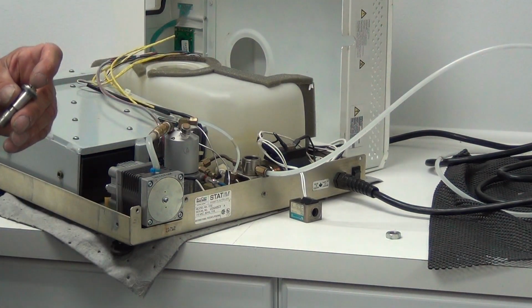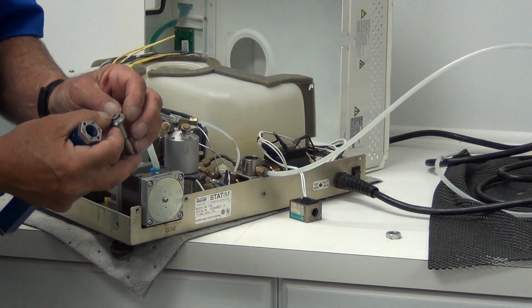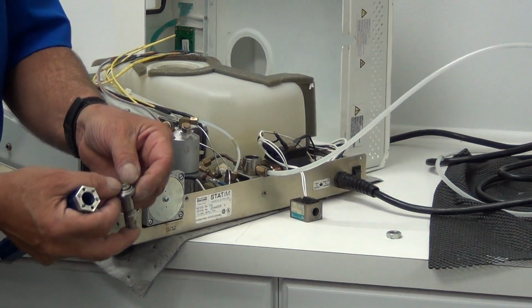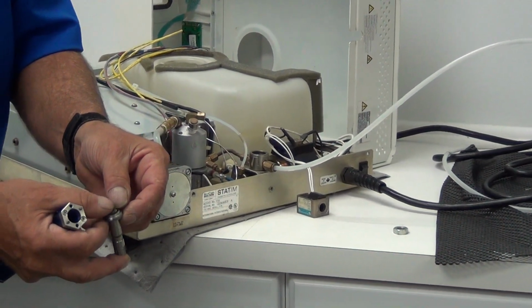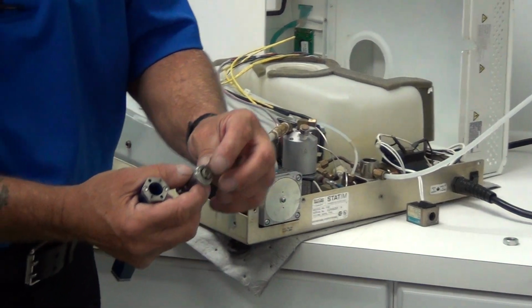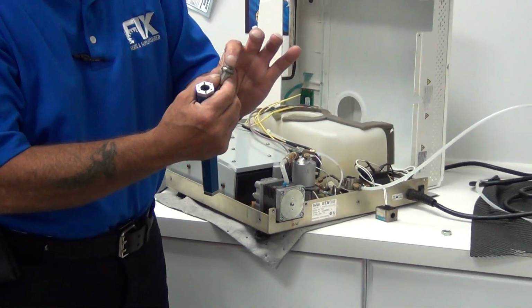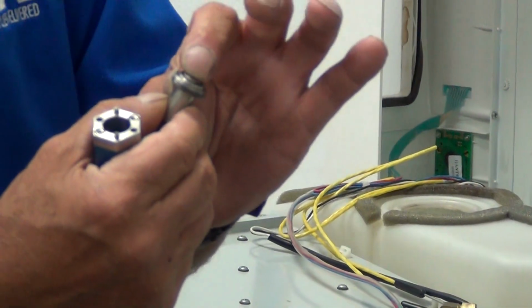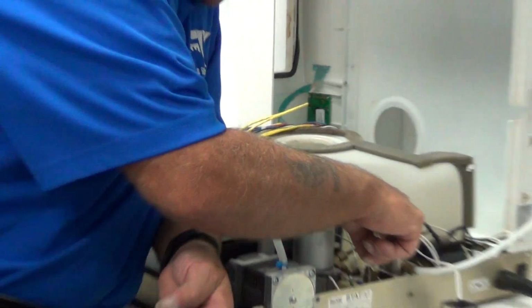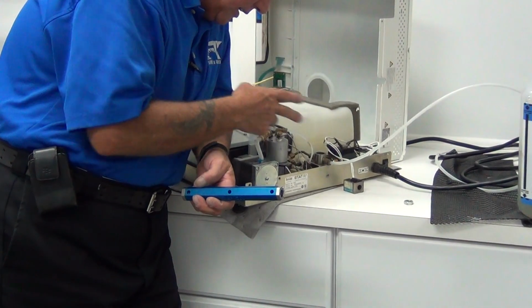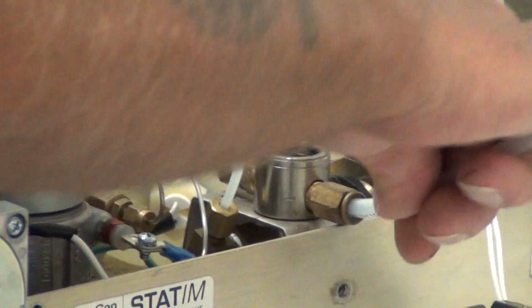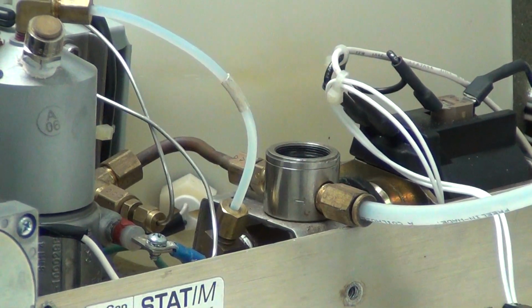Now, we've got the plunger out of the solenoid. We're inspecting the plunger for debris, pieces of debris, cuts in the seat, and resilience and springiness of the piston. And everything seems to be good. We're examining the inside as well for debris. The O-ring looks good, no debris present. We're going to check our hose while we're back here.